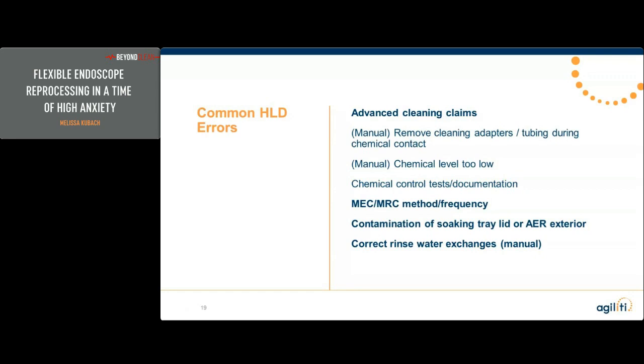So I always tell everyone to pay attention to that. Also, correct rinse water exchanges if you are doing manual cleaning. When I see someone doing manual cleaning, I usually always stay and wait to watch them reprocess a scope. Because while it all sounds good, when it comes down to how they rinse, sometimes they're going back into sinks that are not clean. Sometimes they are carrying and dumping water for their water exchanges, and some just aren't doing the full water exchanges per their chemical.